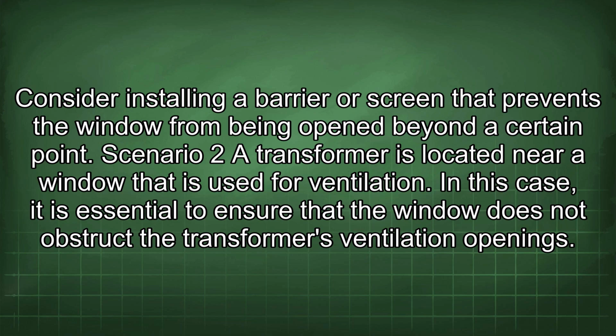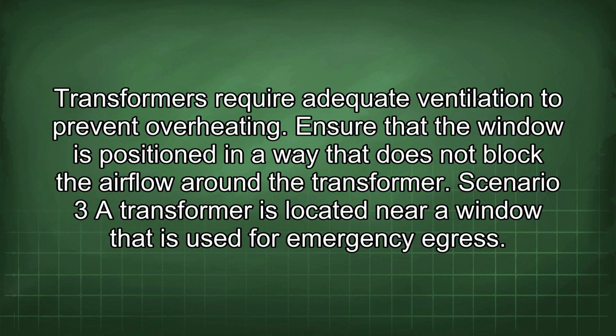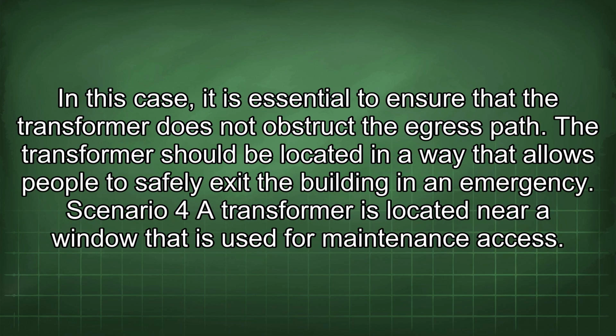Scenario 2: a transformer is located near a window that is used for ventilation. In this case, it is essential to ensure that the window does not obstruct the transformer's ventilation openings. Transformers require adequate ventilation to prevent overheating. Ensure that the window is positioned in a way that does not block the airflow around the transformer. Scenario 3: a transformer is located near a window that is used for emergency egress. In this case, it is essential to ensure that the transformer does not obstruct the egress path. The transformer should be located in a way that allows people to safely exit the building in an emergency.